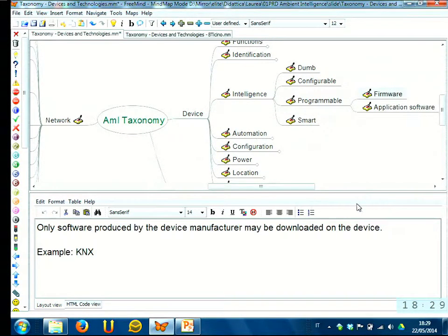First is when a device can be upgraded through a firmware update. So for example, in Konnex, when you buy new devices with the configuration tool, you just connect to the gateway, the device is on the bus. You connect with your PC to the gateway and download from the manufacturer of the device the latest version of its binary code into the PC, and you send it through the gateway to the device. And the device will load the new version of the software that maybe has some bug fixes, has some new functionalities or whatever.